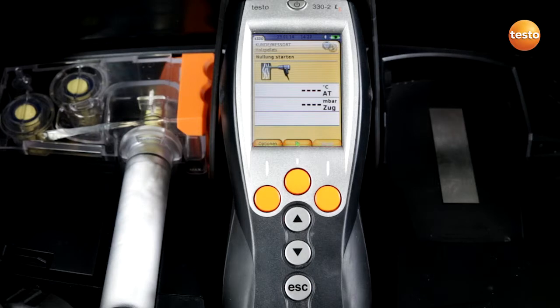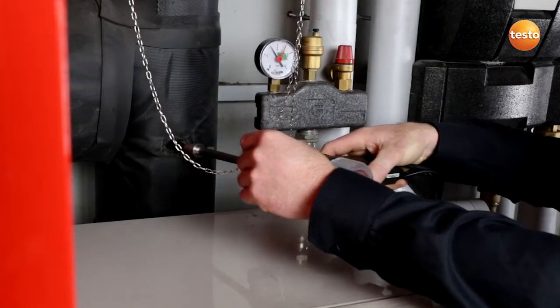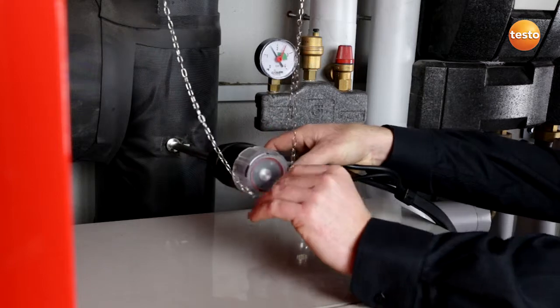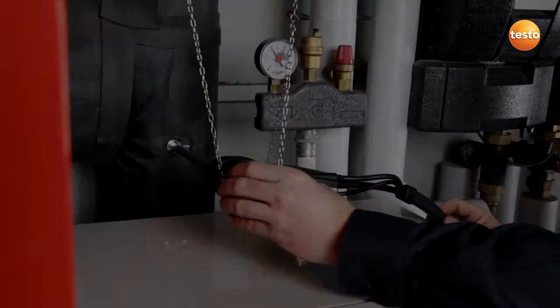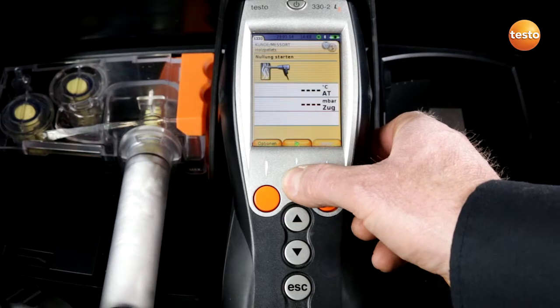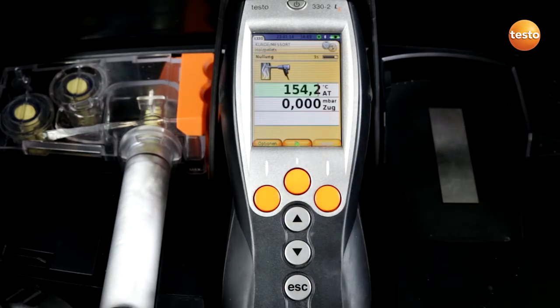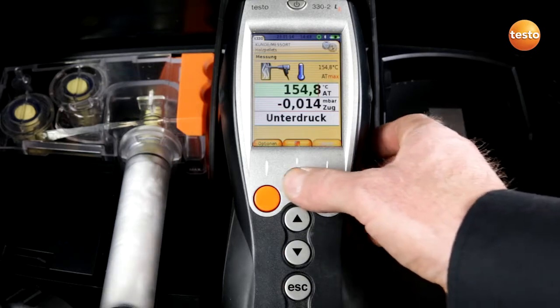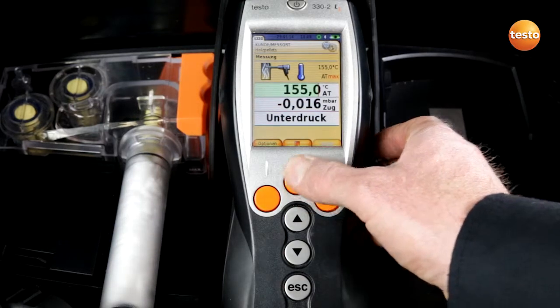and insert the probe into the gas flue. Now I press the green button and begin the flue gas temperature measurement and at the same time the determination of the draft. Draft zeroing starts and the flue draft is measured. After I've determined the draft, I press the middle button and the values are saved.